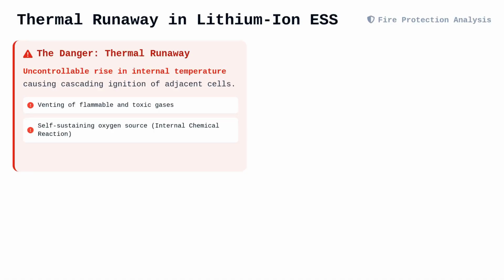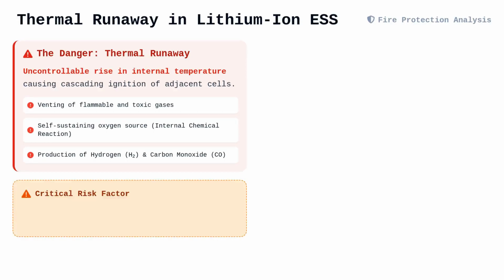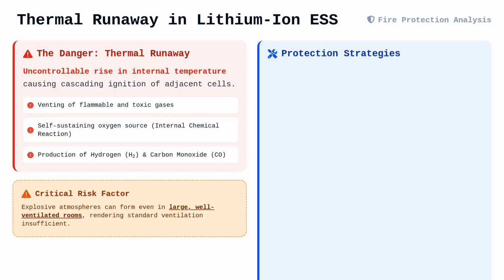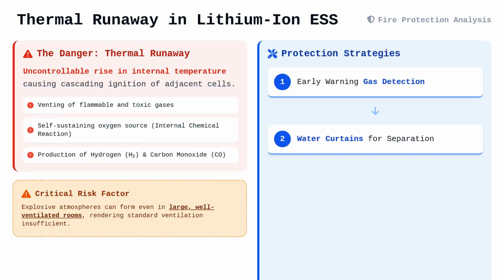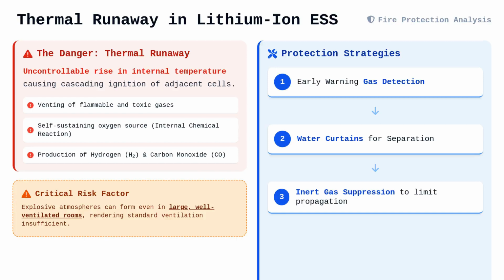Unlike a simple hydrocarbon fire, thermal runaway creates its own oxygen source and produces significant quantities of hydrogen and carbon monoxide, which can lead to explosive atmospheres even in large, well-ventilated rooms. Protection strategies must evolve beyond standard sprinklers to include early warning gas detection and, potentially, water curtain separation or inert gas suppression to limit the propagation of the event.